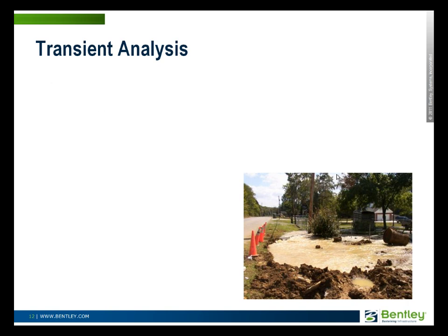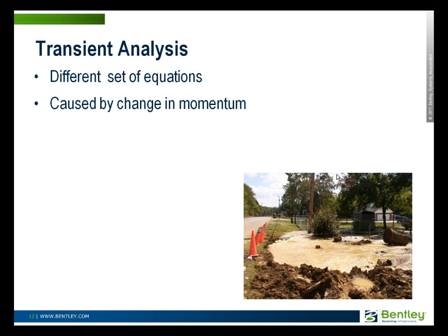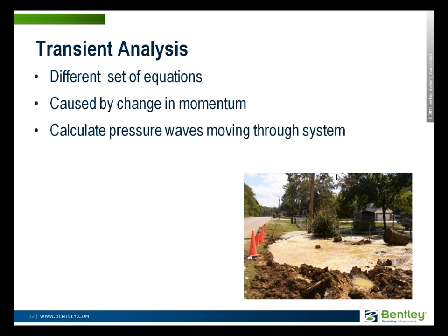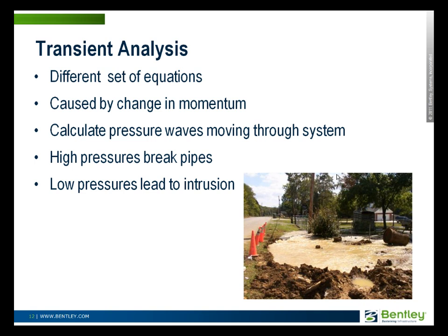Another type of analysis is transient analysis. In this kind of analysis you're solving a whole different set of equations, looking at the fact that whenever the momentum of the water changes in the pipes, pressure waves are created. This goes back to Newton's second law — F equals MA. When you change the momentum you exert a force, and when that happens you create waves that move through the system and can do a lot of damage. High pressures from these transients can break pipes. You can also have very low pressures — even negative — and if you have any cracks or breaks in the pipes, these can lead to intrusion of water from outside into the distribution system piping network. For transient analysis you would use the HAMMER program, as opposed to WaterGems, because HAMMER solves the different set of equations that relate to transient analysis.